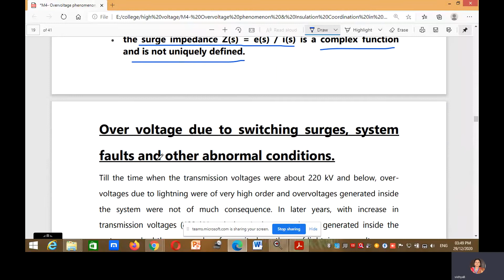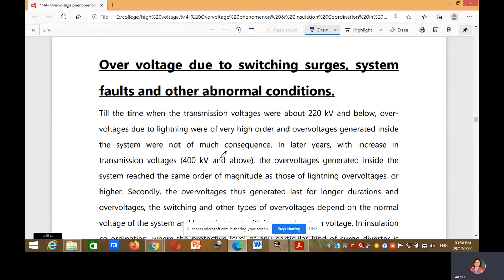But until the time when transmission voltages were about 220 kV and below, what about the overvoltage? Overvoltage due to lightning waves, which are of very high order, and overvoltages generated inside the system were not of much consequence. In later years, with the increase in transmission voltage, the overvoltages generated inside the system reached the same order of magnitude as lightning overvoltages or higher. Secondly, the overvoltages thus generated last for long durations. The switching and other types of overvoltage depend on the normal voltage of the system and hence increase with the increased system voltage.